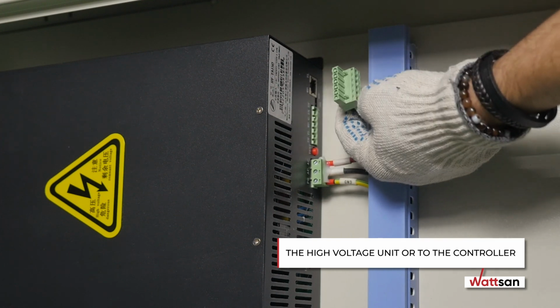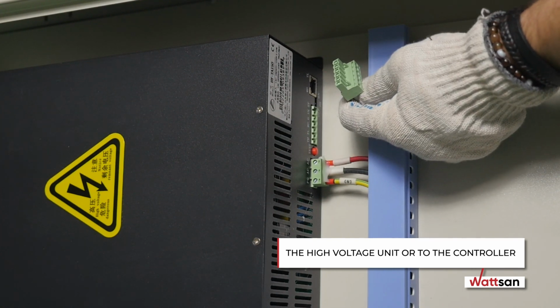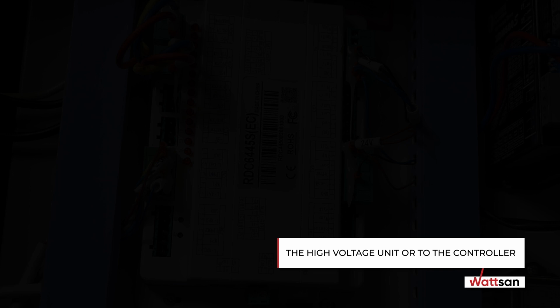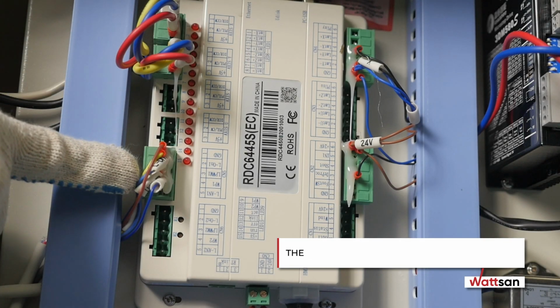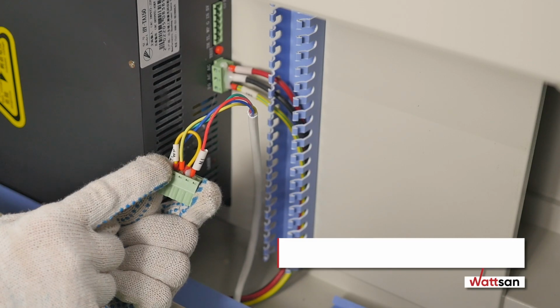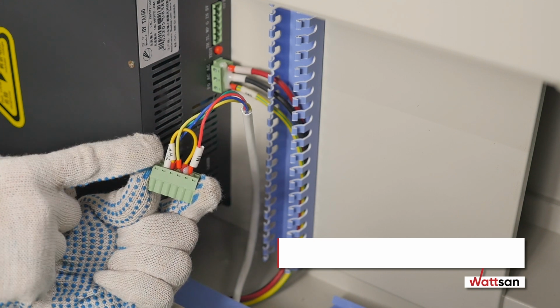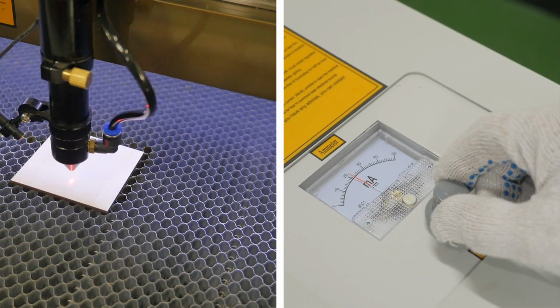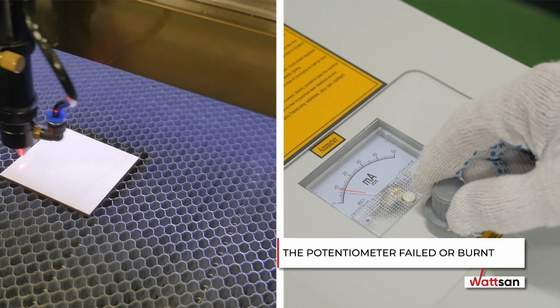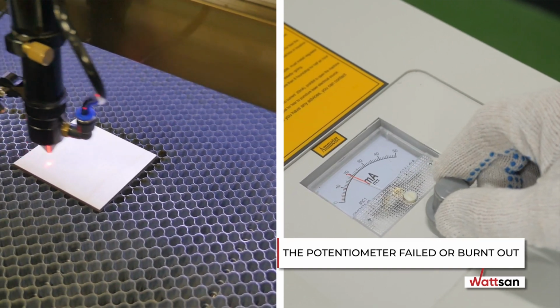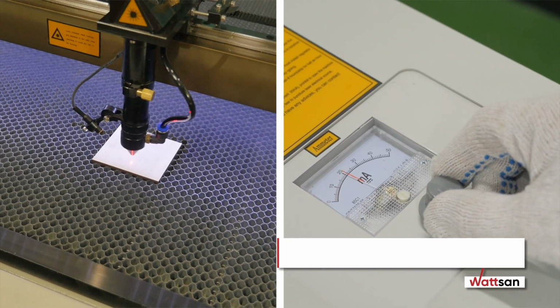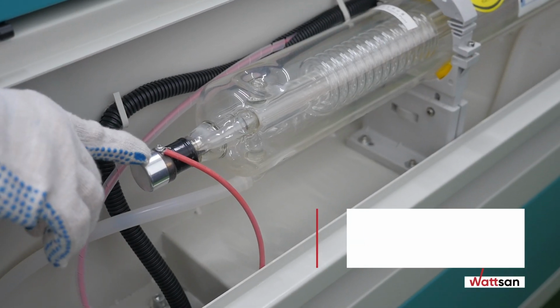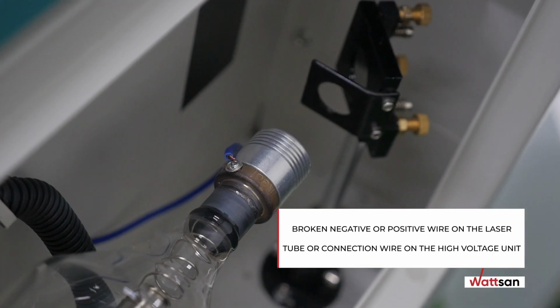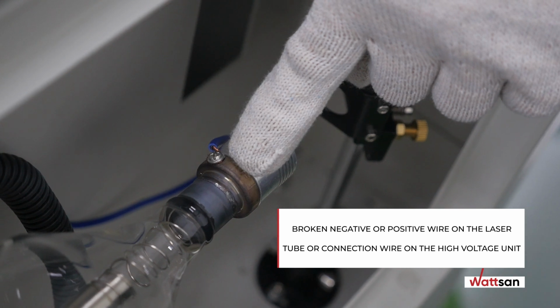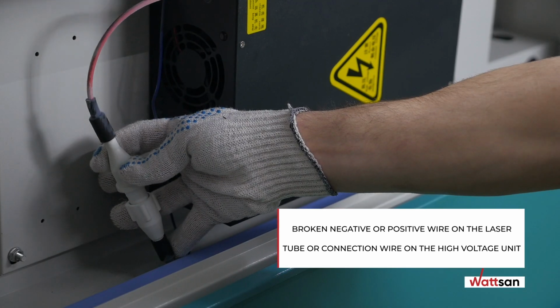5. Loose or badly wired connection to the high voltage unit or to the controller. 6. No jumper on the high voltage unit. 7. The potentiometer failed or burnt out. No reaction when turning the potentiometer knob. 8. Broken negative or positive wire on the laser tube or connection wire on the high voltage unit.